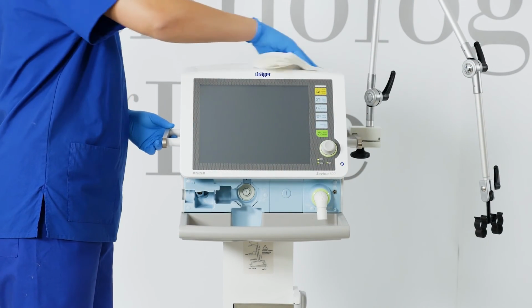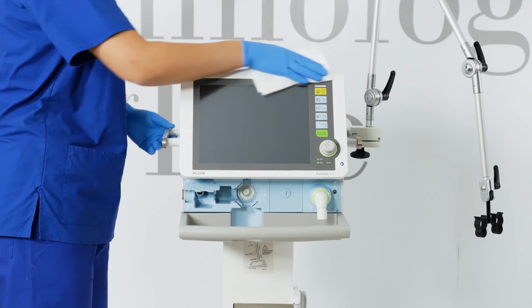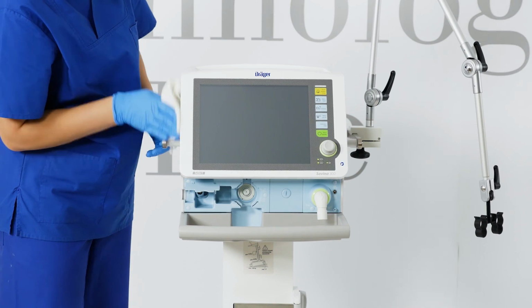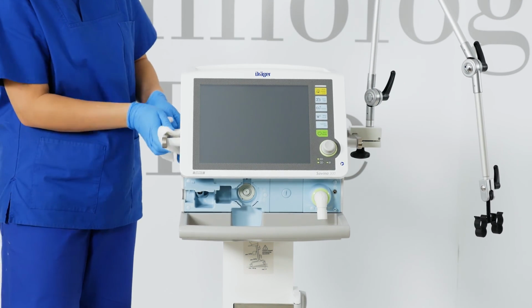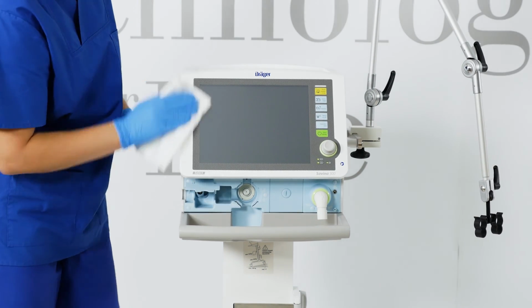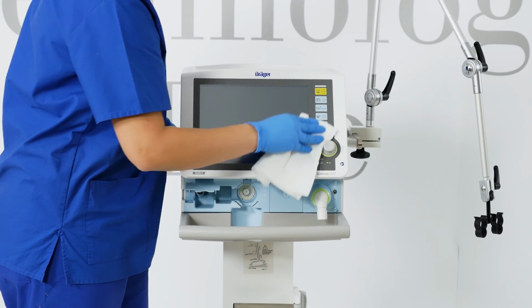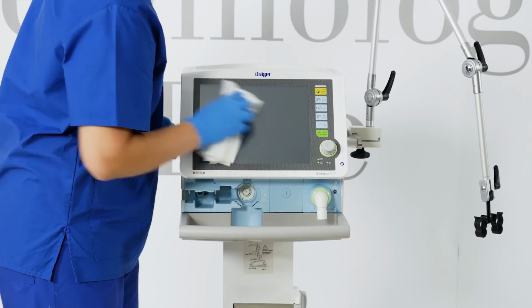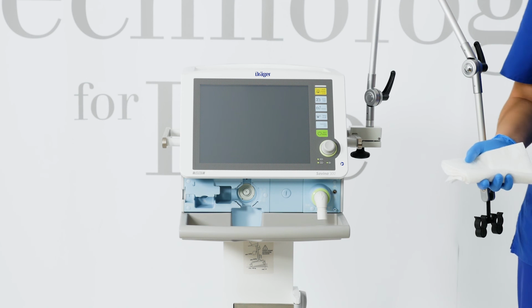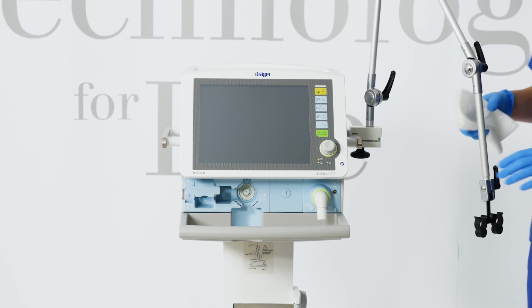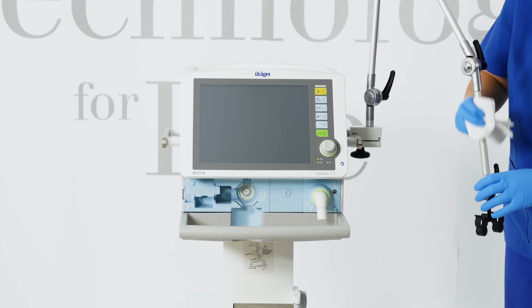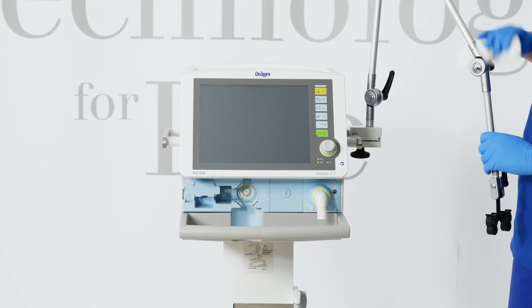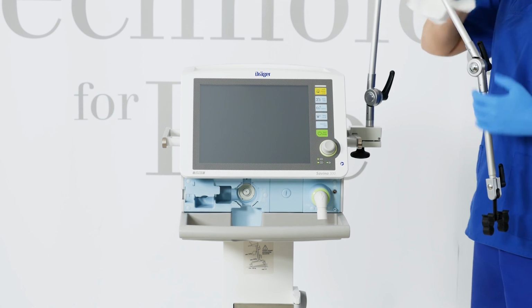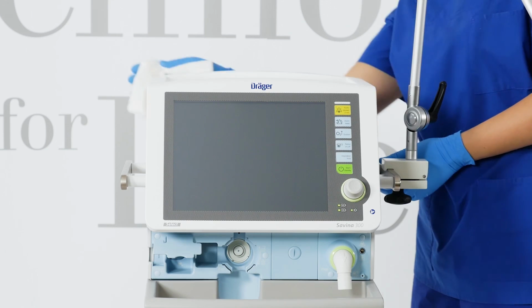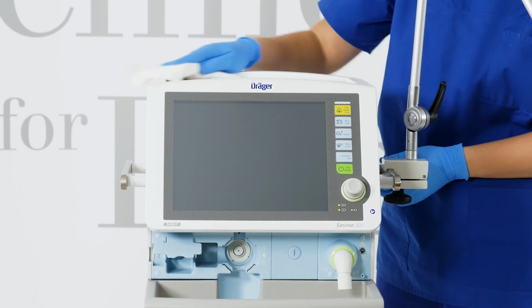Now wipe the surfaces with a clean, damp, lint-free cloth without using corrosive detergents. Wipe surfaces until they are free of all spots and dry them. Manual disinfection should preferably be carried out with disinfectants recommended by Dräger. Please note that the concentration, temperature, and exposure times are different with every disinfectant. Please consult the individual manufacturer's instructions for use.